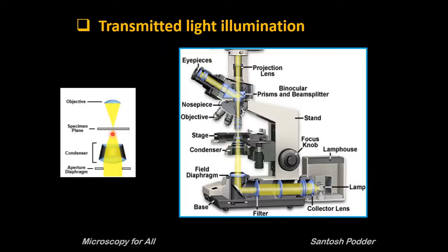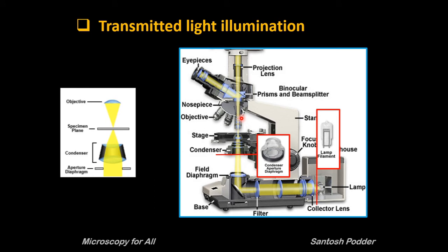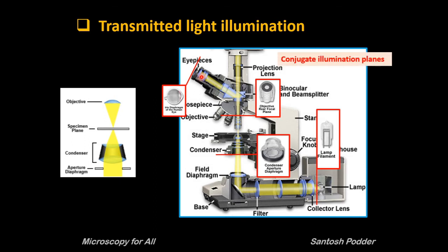The condenser projects a cone of light to illuminate the field of view in the sample. Parallel light rays that pass through and illuminate the sample are brought to focus at the back focal plane of the objective, where the image of the lamp filament and the condenser aperture diaphragm will be seen in focus — that is why these three planes are called conjugate planes. We have another aperture plane at the exit pupil of the eyepiece, which appears to hang in space a few millimeters above the eyepiece. This is simply the image of the illuminated rear aperture of the objective. So all four planes are conjugate illumination planes.